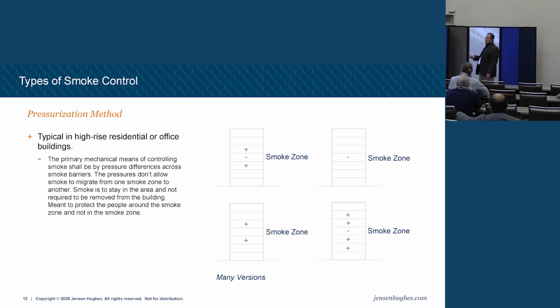You can tell really quickly, though, if the mechanical systems are evolving and the contractor working on the mechanical system doesn't do fire protection for a living, they may lose that sequence of operations. And that's the most common thing we see fail in these atrium systems and high-rises over the years: facility managers didn't understand that fire protection is there, right? So we would like for facility managers to be fire protection advocates. Understand that everything in your building may have dual purpose. And if you don't know, ask experts to come in and give you an assessment.